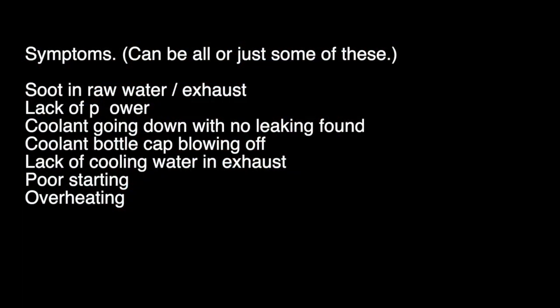Let's look at some of the classic symptoms. Soot in the raw water or in the exhaust water is really a telltale sign that the engine isn't breathing correctly, and that's normally a blocked or partially blocked exhaust elbow. Other signs are a lack of power, coolant going down with no leaking found on the outside of the engine, the coolant bottle cap blowing off, a lack of cooling water in the exhaust, poor starting, or even overheating.